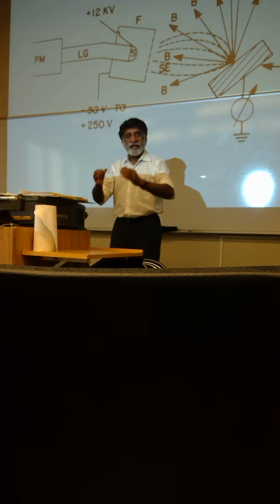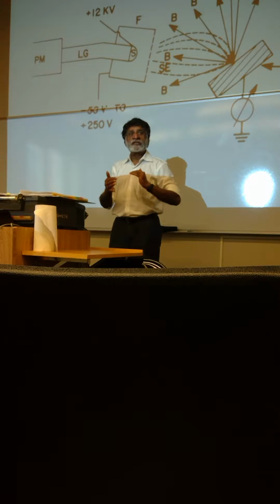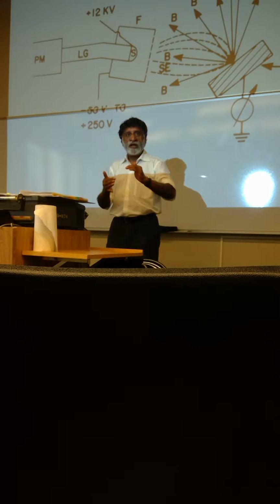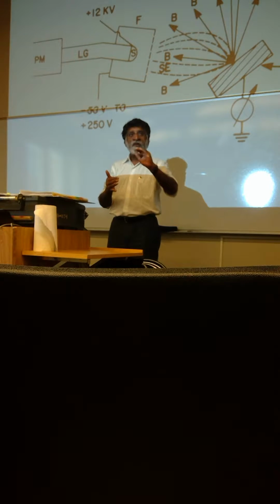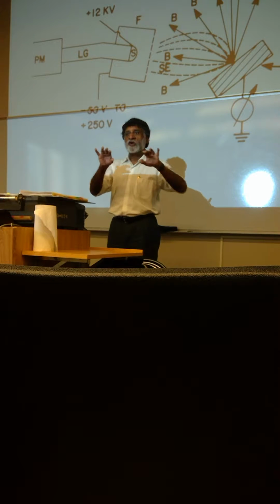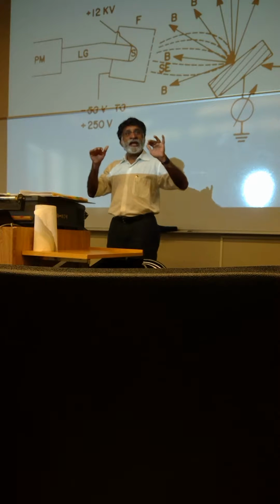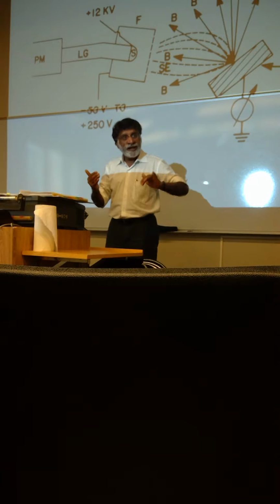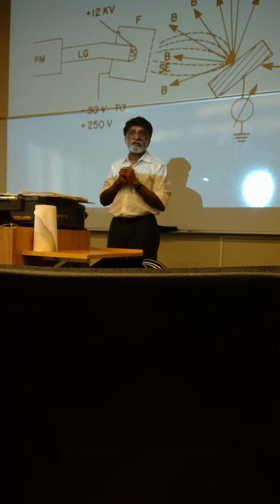The secondary electron: the primary or the fast electron that is coming down the column, 20 kiloelectron volts, interacts with the sample and generates secondary electrons. And we know that the depth at which the secondary electrons come out is only a very shallow depth. You can create a scanning image either using the secondary electrons or using the backscattered electrons.